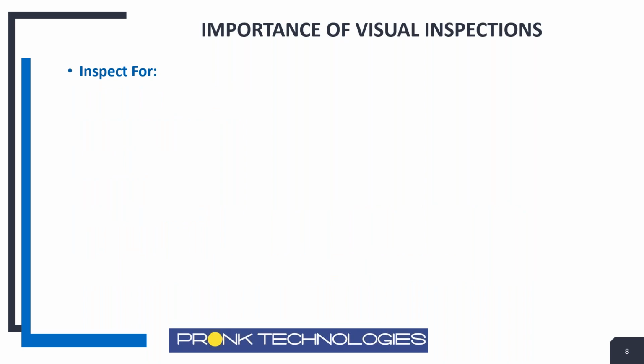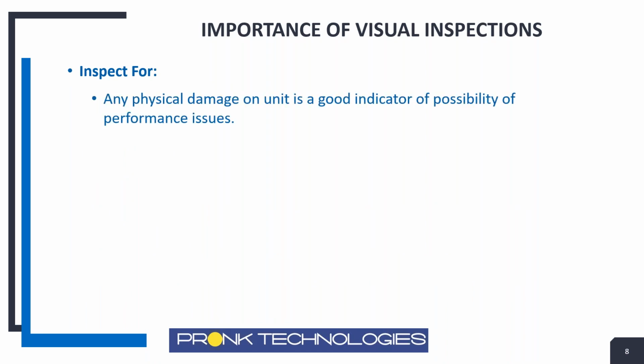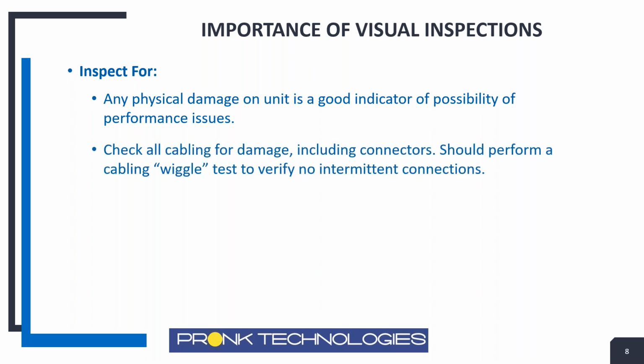So in terms of doing the defibrillator, of course, this really applies for all medical devices, but for defibrillators, it's even more critical is the visual inspections. You want to make sure you're always doing good visual inspections on the units. It's specified numerous times in the service manual itself. Physical damage is something that we really need to pay particular attention to. You may see some physical damage on the exterior part of the unit, but it also could lead to probable problems performance-wise. So any physical damage is a good indicator that you may need to look at this more thoroughly because it could impact performance of the device.